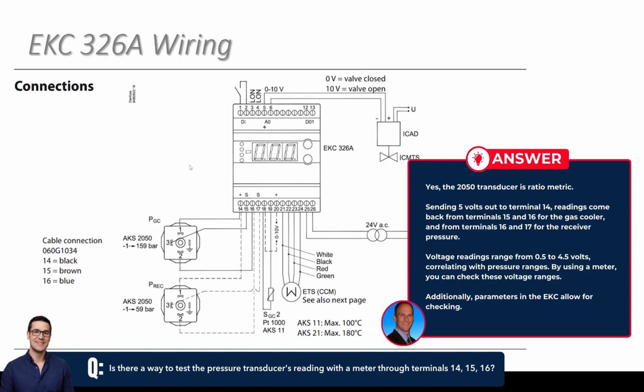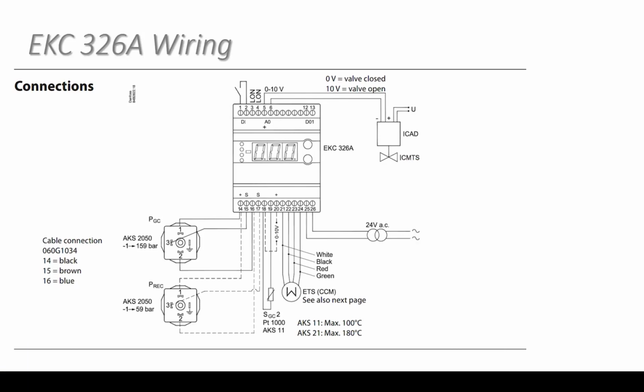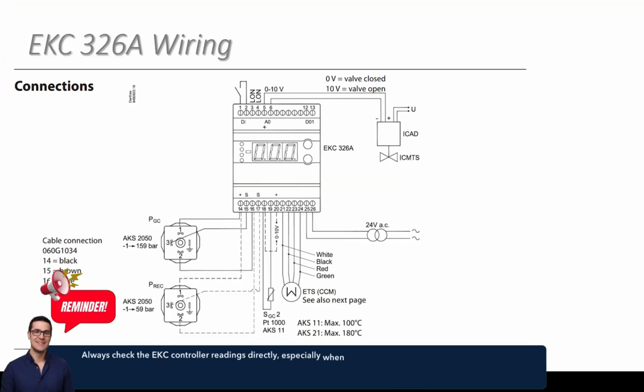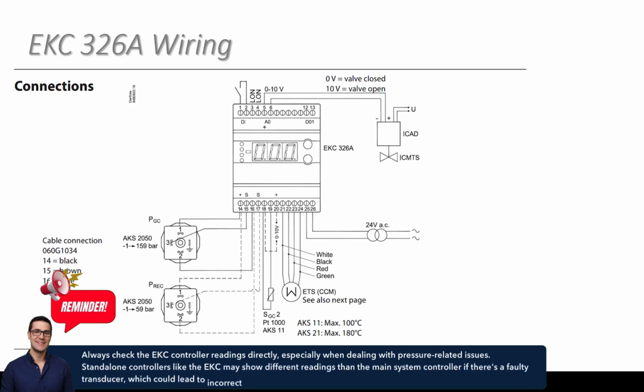Yeah. Okay, perfect. Because I've seen it before where there was a failed transducer, for an example, and the technician was reading off the controller of the system, but not the EKC, because this is standalone. They were thinking it was reading this pressure. It actually was reading the wrong pressure, and that's why the high pressure valve would not open, because they had a faulty pressure transducer on the system, but on the main controller, it was saying a different pressure. So you always have to check this controller because it is a standalone controller.